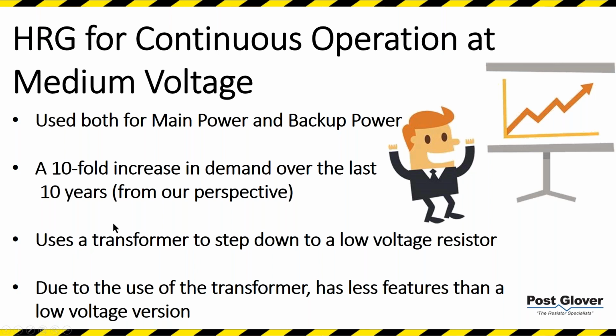We do use a transformer to step down, and when I say we, I don't know of anyone, although people are coming out with new things all the time, who actually doesn't use a transformer in a medium voltage high resistance ground system. But we do so because we actually tried to do one without a step down transformer. There are some benefits of not using a transformer. You don't have isolation, so you can do things like capacitive charging current. There's neutral monitoring, etc., that you would have a hard time doing with the transformer.